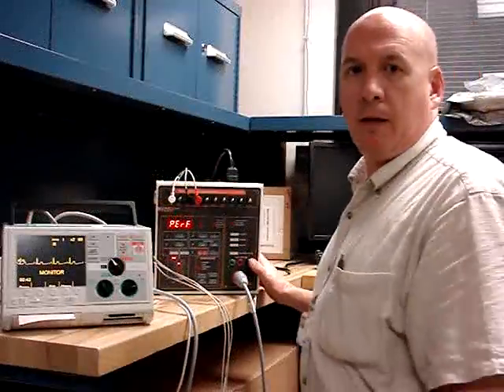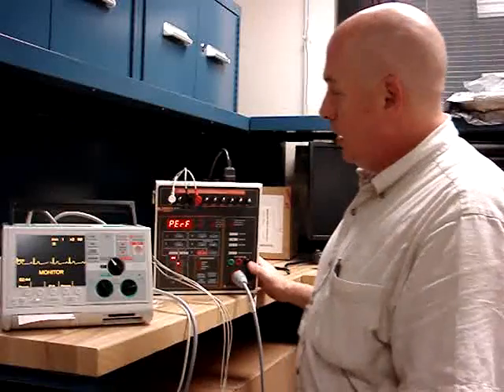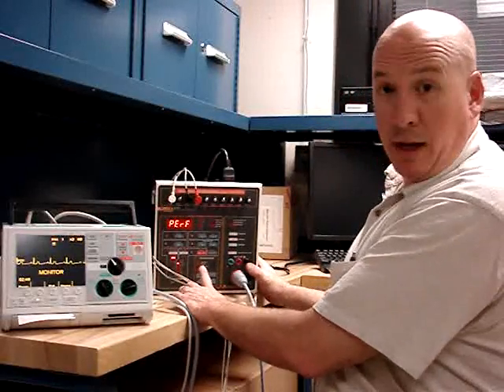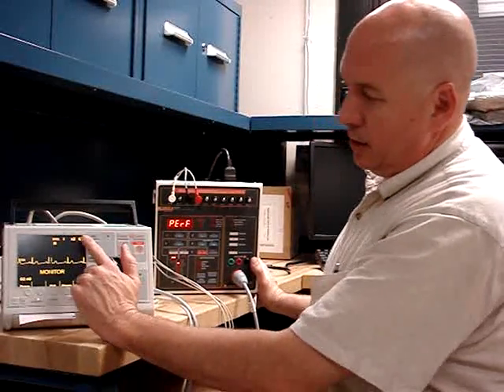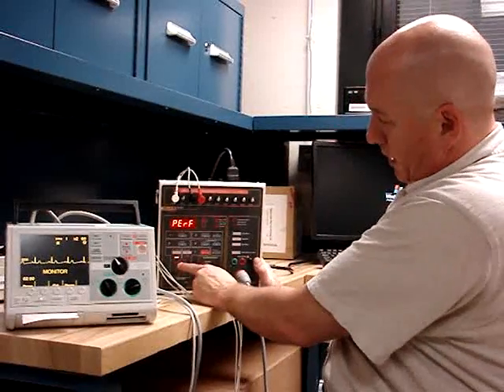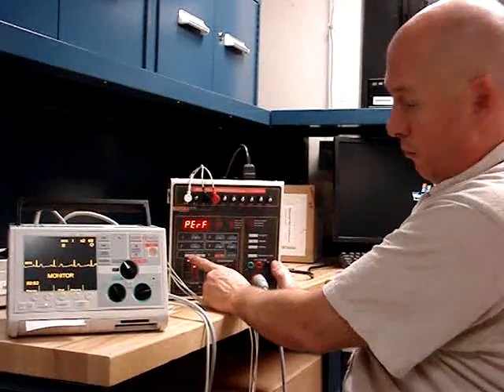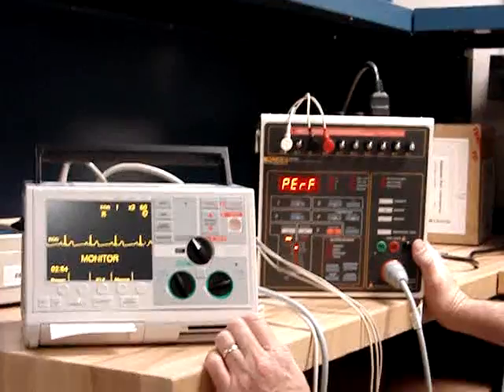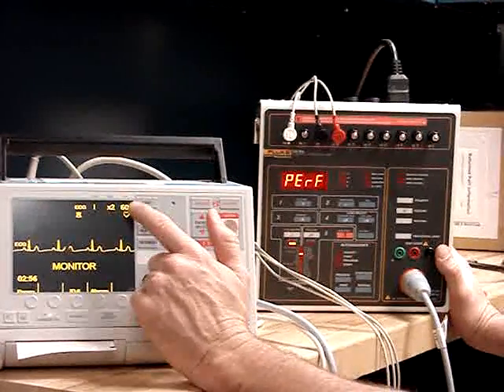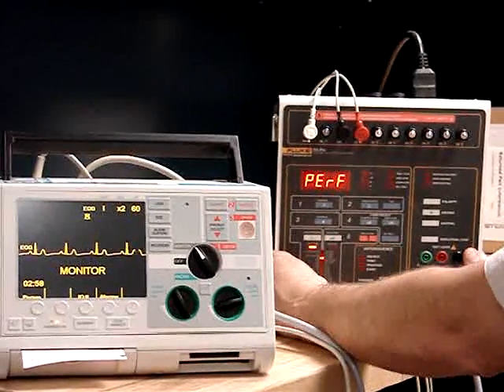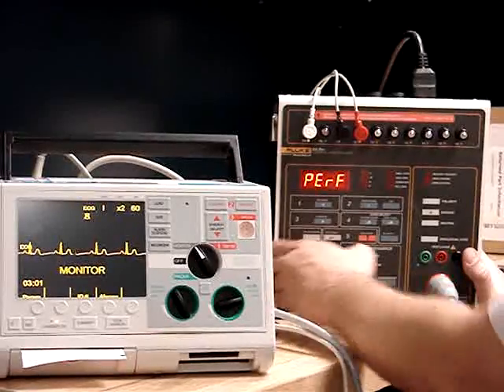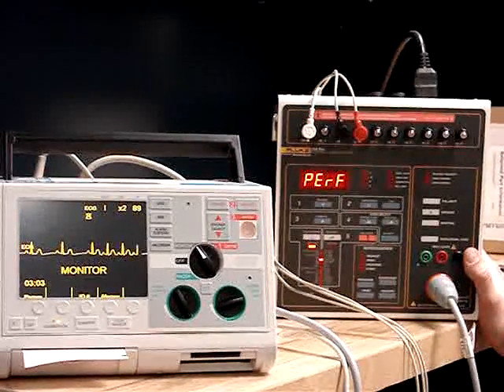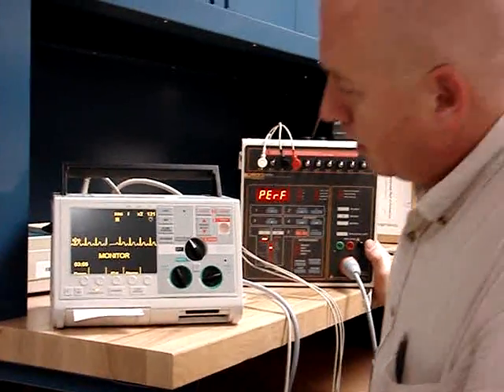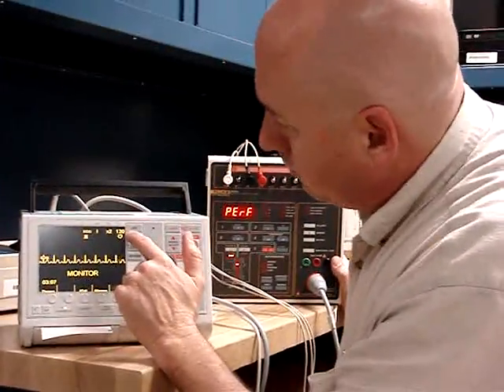Now we're doing the rate calibration procedures. We're going to use the safety analyzer for this. It should be 60 beats per minute, which we have this set at. We're in the ECG performance, and it should be plus or minus 5. So we are at 60, so we're good there. And now we're going to do it at 120. Now we are right at 120, and again it's plus or minus 5.